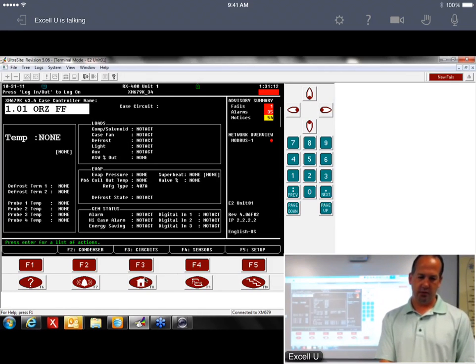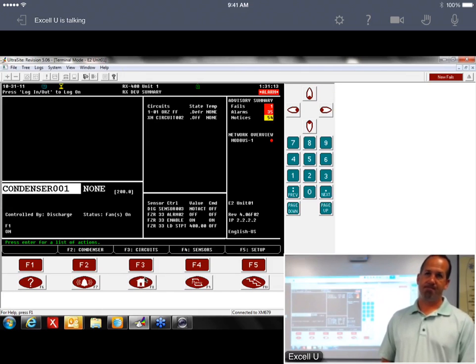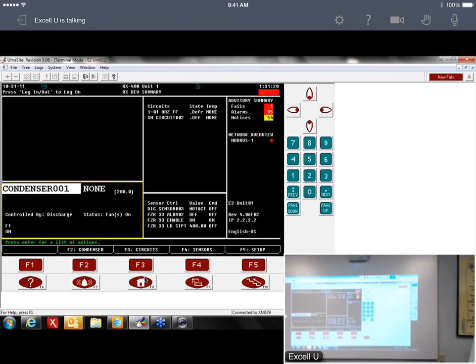The controllers - are they addressed? Are they hard addressed, meaning dip switches, or how are they addressed? No, we address them from here, through the E2, and then we commission it in the E2 to bring it online. So if you're commissioning a new store, you'd have to tell all the controllers their numbers, correct, then go to the rack, communicate, talk, and download their parameters. Right. And if I was to stock these - basically a generic controller - there's no way the parameters would have to be downloaded from the pull-down to the E2. Correct, yeah, if you were to stock them.